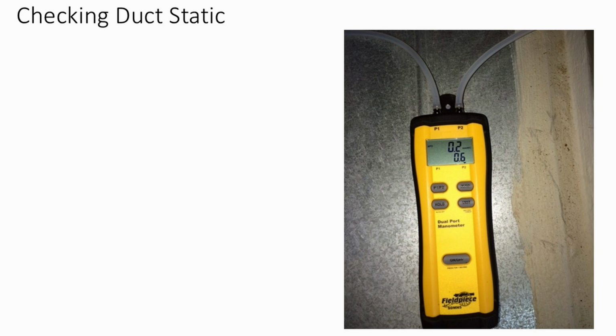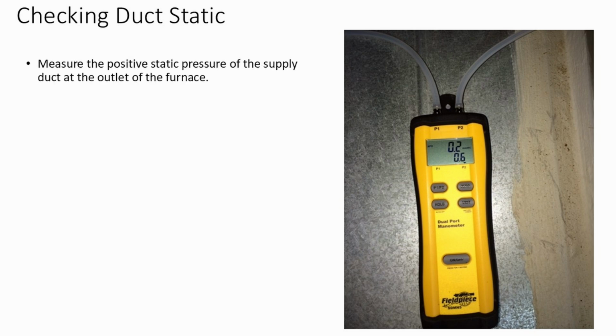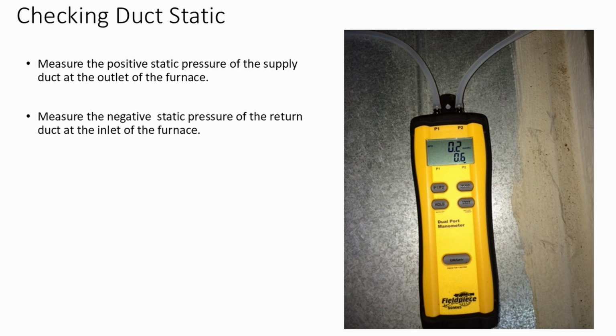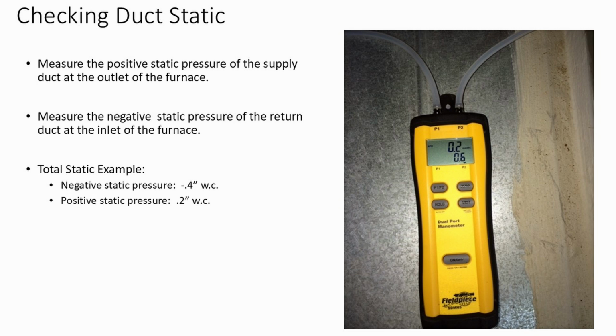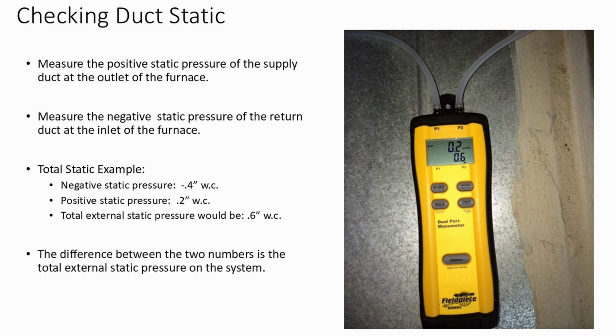When checking duct static, measure the positive static pressure of the supply duct at the outlet of the furnace. Measure the negative static pressure of the return duct at the inlet of the furnace. Your total static pressure example would be with a negative static pressure of minus 0.4 inches water column and a positive static pressure of 0.2 inches of water column. The total external static pressure would be 0.6 inches of water column. The difference between the two numbers is the total external static pressure of the system. Disregard the negative in front of the negative static pressure and just add the two numbers together.